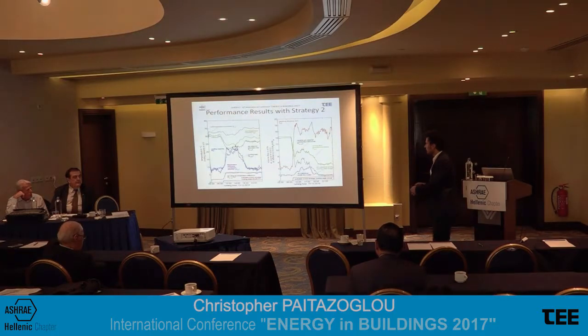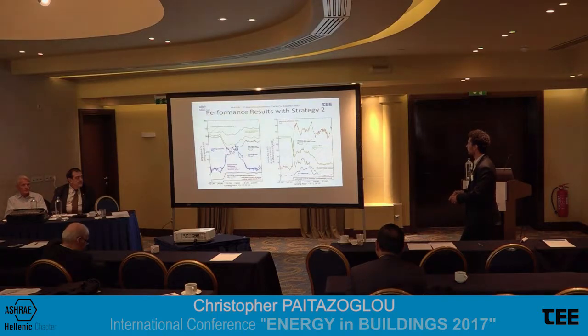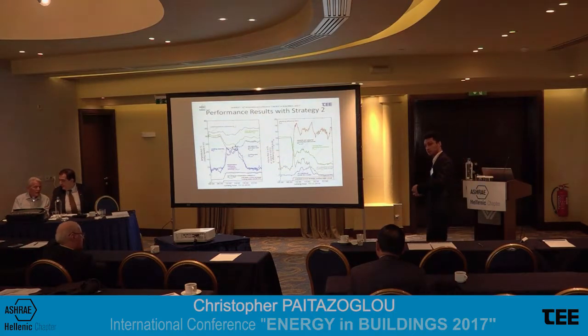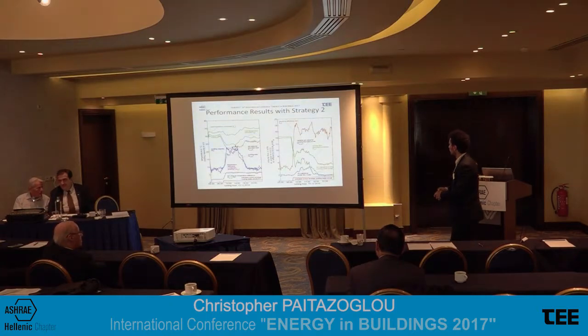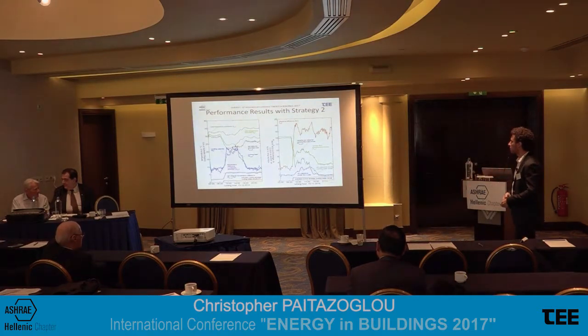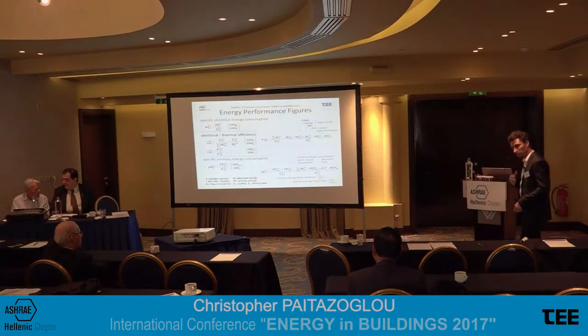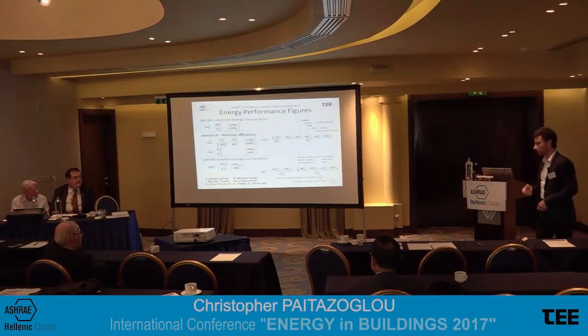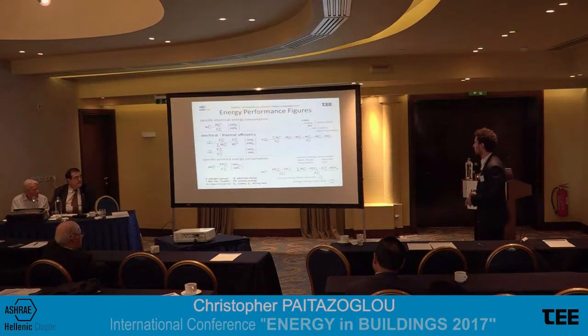So then, at 8 o'clock here, 2 effects take place. One, the cooling load is increasing, goes up to 20 kilowatts, which is successfully covered by the absorption chiller. And the second effect is that the strategy is being activated, leading to a decrease of the volume flow by keeping this temperature difference that is fixed at 6 Kelvin constant. As a result, you see that the COP is increasing to 16 and is being kept constant throughout the night and the following days. So this is a very efficient way of reducing the consumption in the recooling circuit.